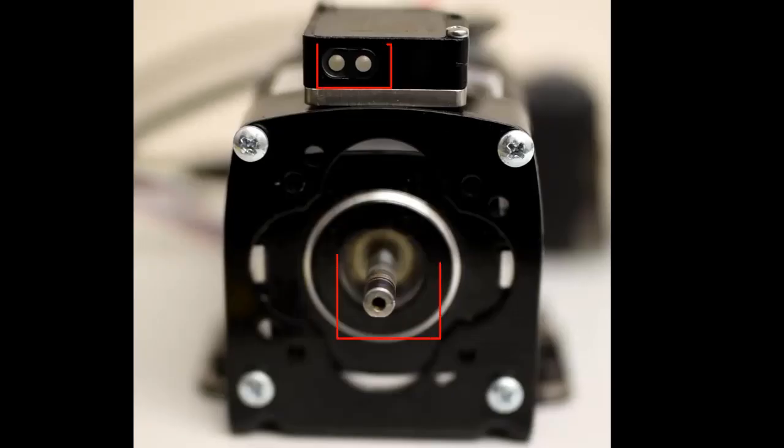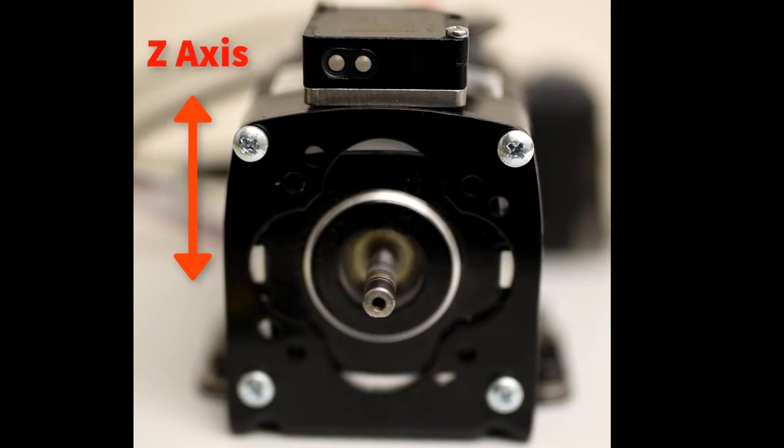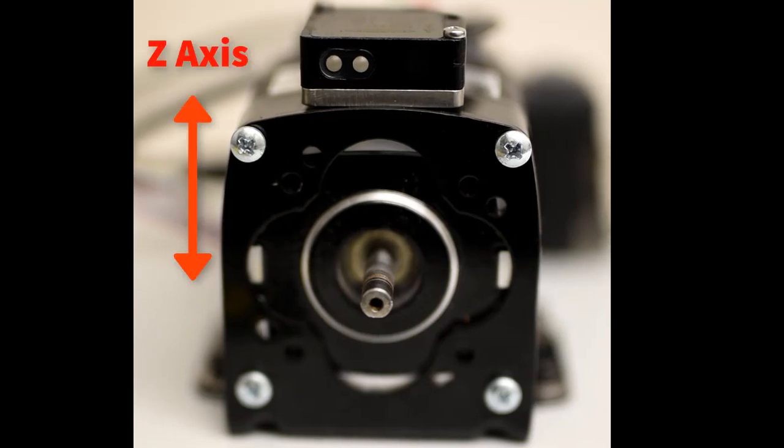An easy way to remember this is to make sure that the vibration sensor's LEDs are pointing in the same direction as the shaft as shown. Mount the sensor horizontally so that the z-axis points towards the shaft.